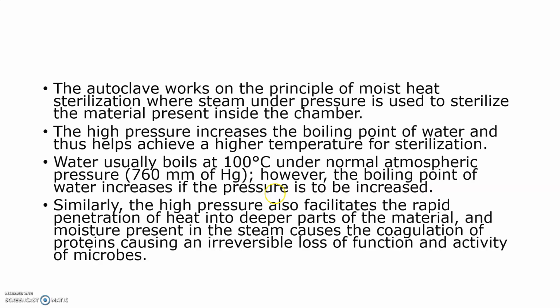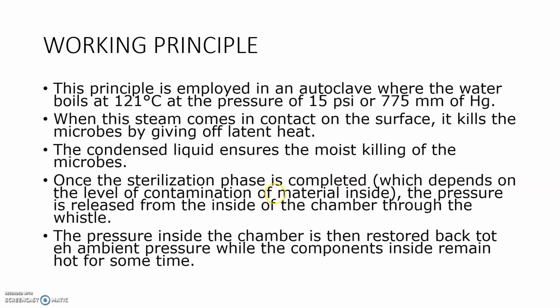Similarly, high pressure facilitates a rapid penetration of heat into the deeper parts of the material, and moisture present in the steam causes the coagulation of protein, causing irreversible loss of function and activity of microbes. The working principle mainly employed is that water boils at 121 degrees Celsius at a pressure of 15 psi or 775 millimeter of mercury. When the steam comes in contact with the surface, it kills the microbes. How? By giving off latent heat. The condensed liquid ensures the moist killing of microbes.